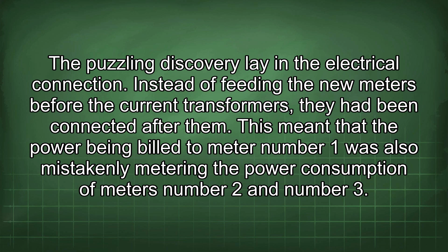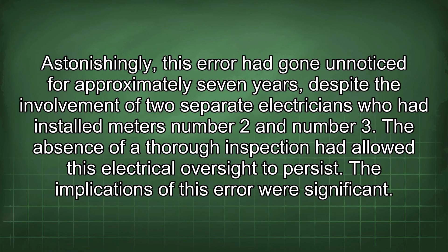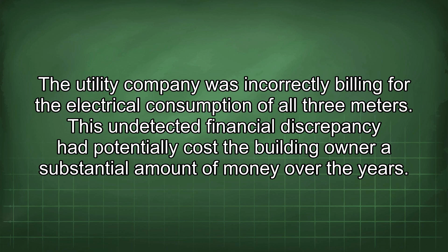Astonishingly, this error had gone unnoticed for approximately 7 years, despite the involvement of 2 separate electricians who had installed meters number 2 and number 3. The absence of a thorough inspection had allowed this electrical oversight to persist. The implications of this error were significant. The utility company was incorrectly billing for the electrical consumption of all 3 meters. This undetected financial discrepancy had potentially cost the building owner a substantial amount of money over the years.